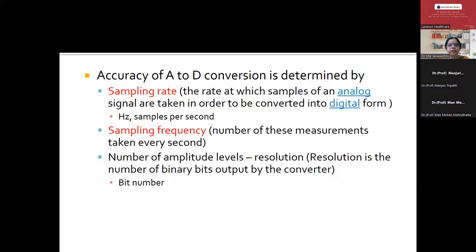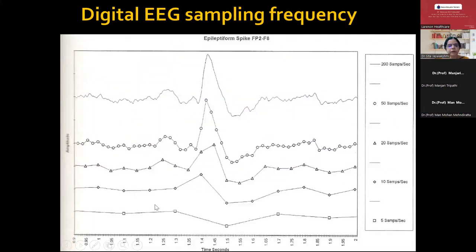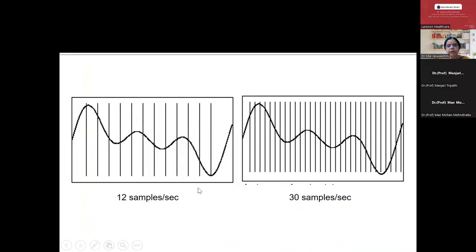Sampling rate is the rate at which the sample of the analog signal is taken to convert to digital form, whereas sampling frequency is the number of measurements taken every second. The sampling rate should always be high. If the sampling rate is very low — at five samples per second — the graph is very poor. At 200 samples per second, we can see real-time recording of EEG activity as well as slow wave activity. Hence the sampling rate should be high — the more the sampling rate, the better the waveform.